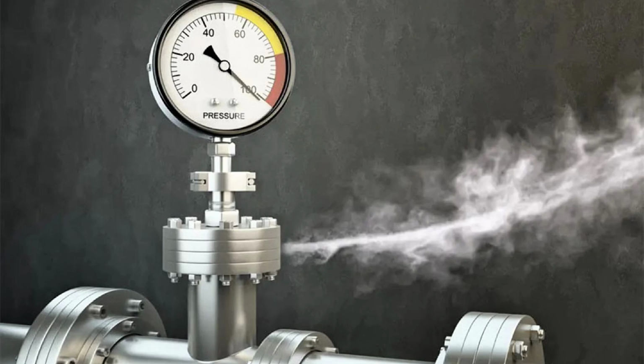ABCBs are also susceptible to air pressure leakage, which can impact their performance and reliability. Air pressure leakage can occur due to a variety of reasons, including seal failure, pipe damage, or valve failure. When air pressure leakage occurs, it can lead to a decrease in the air pressure, which can impact the ability of the circuit breaker to extinguish the arc. This can lead to a decrease in the reliability of the circuit breaker and potentially cause faults or equipment damage.